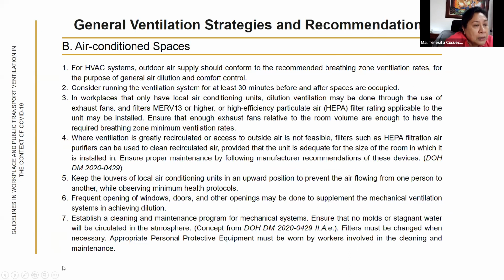Okay. Now, if we look at air-conditioned spaces, the earlier one was on non-air-conditioned. Here on air-conditioned, this is where indoor air quality will really matter, because you would like to have very good indoor air quality. Air is supplied by mechanical means, and there should also be the removal of air through the air handling unit. That is why it is very important that the HVAC system and the outdoor air supply conform to the recommended breathing zone ventilation rates for the purpose of general air dilution and comfort control.